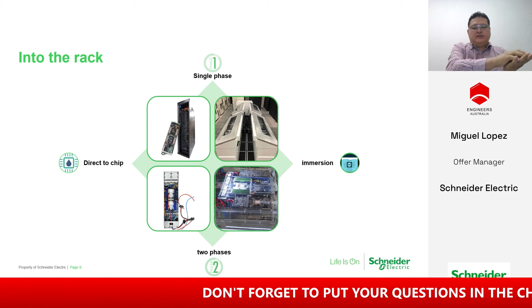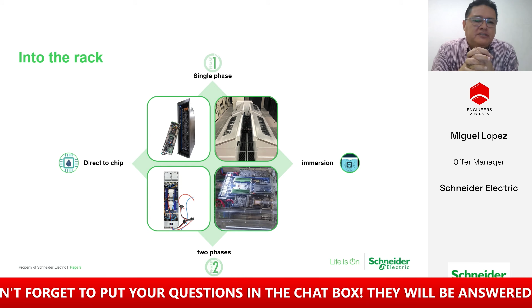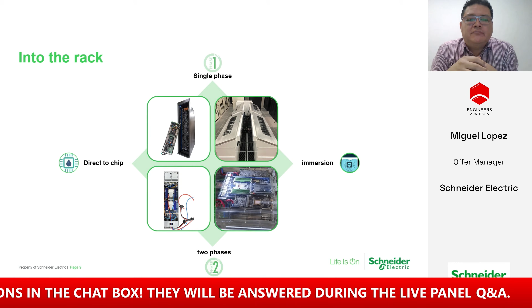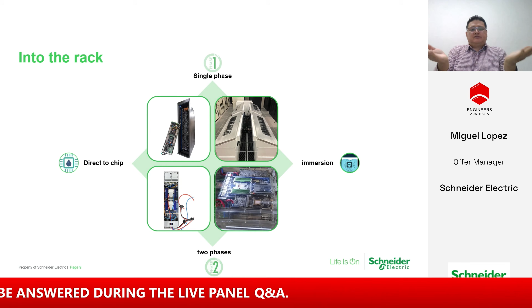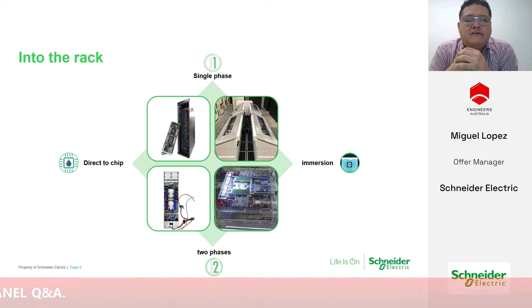So single phase and two phase, understanding that the fluid is either one or the other, there is also so-called direct-to-chip. Direct-to-chip is essentially delivering that water to a cold plate or heat sink that is heat-pasted onto the GPU or CPU. On the right hand of the slide deck is a fully immersion-type system, where the entire motherboard is turned 90 degrees and submerged into a tub or tank of dielectric, non-conductive fluid. This is a preview of what's available in the market at the moment.